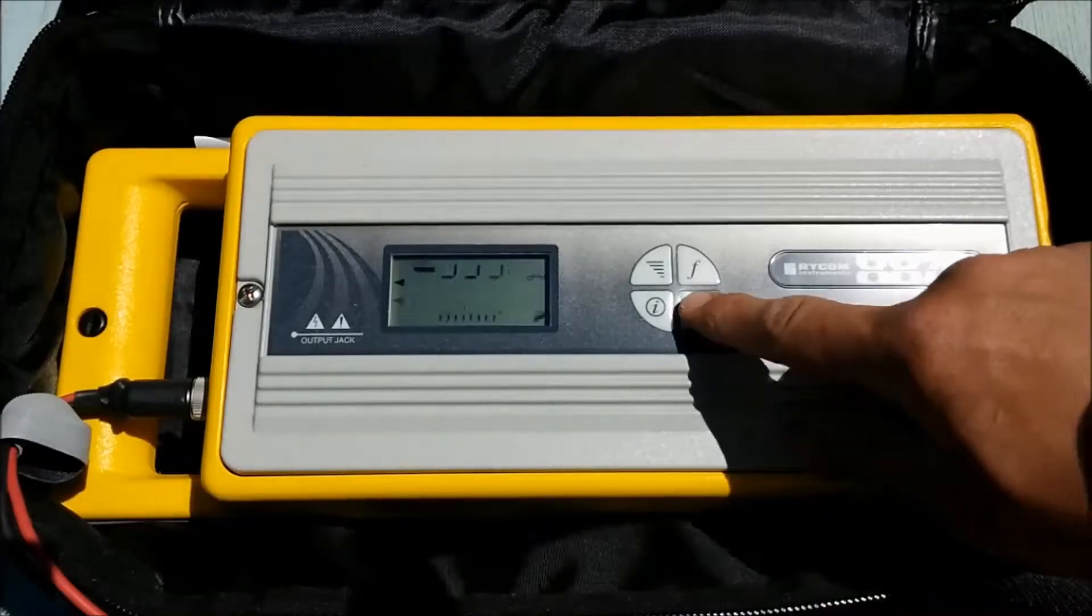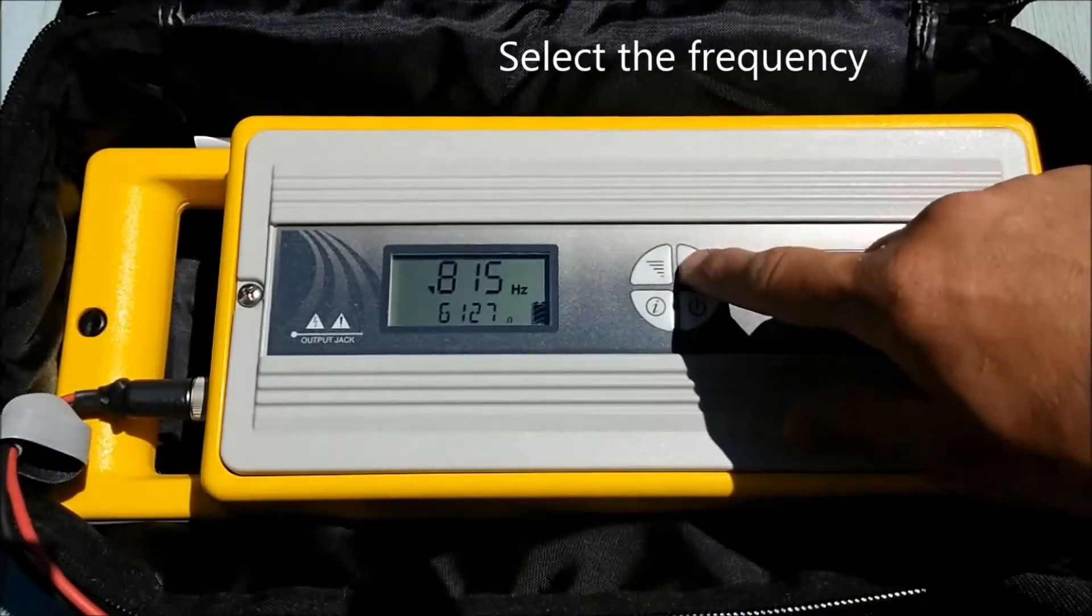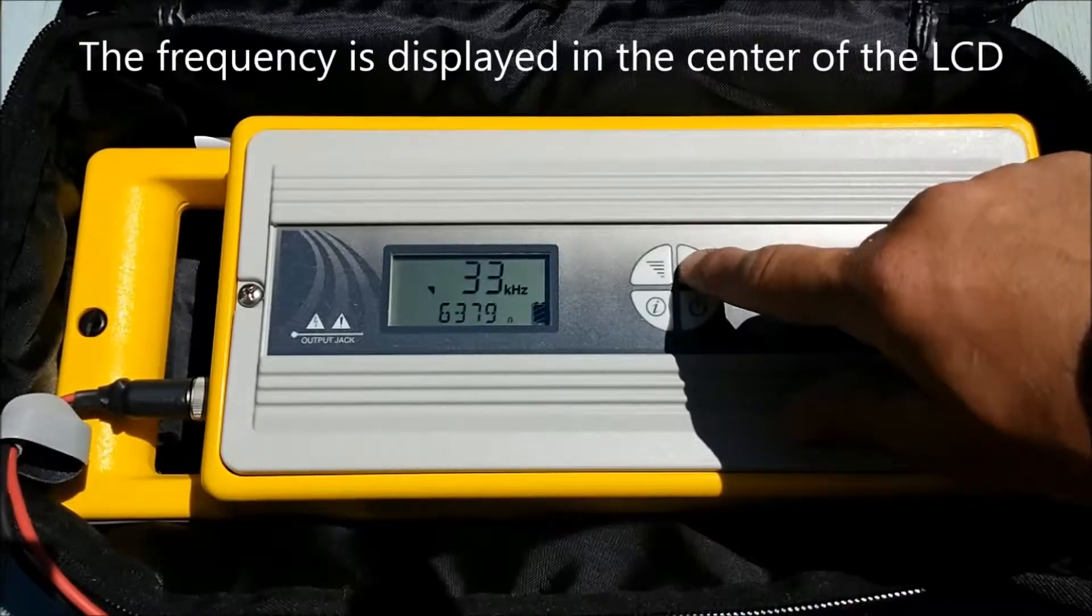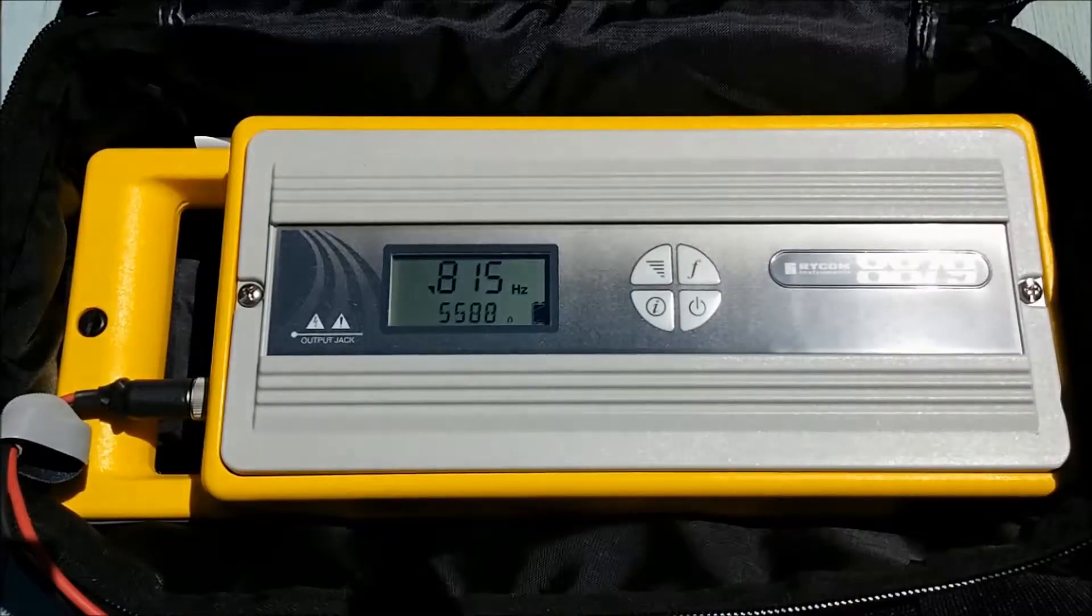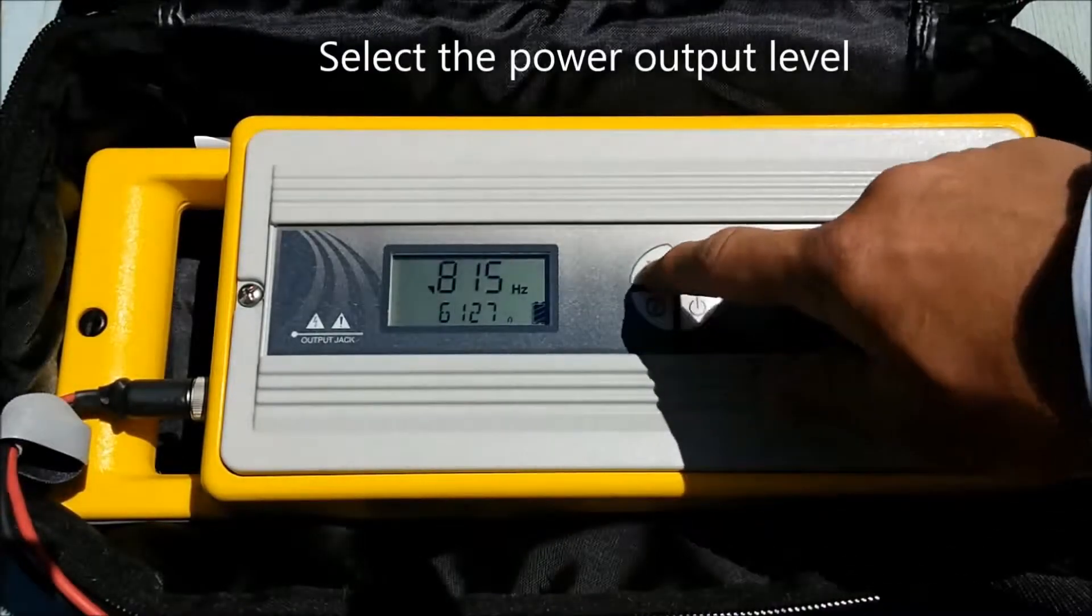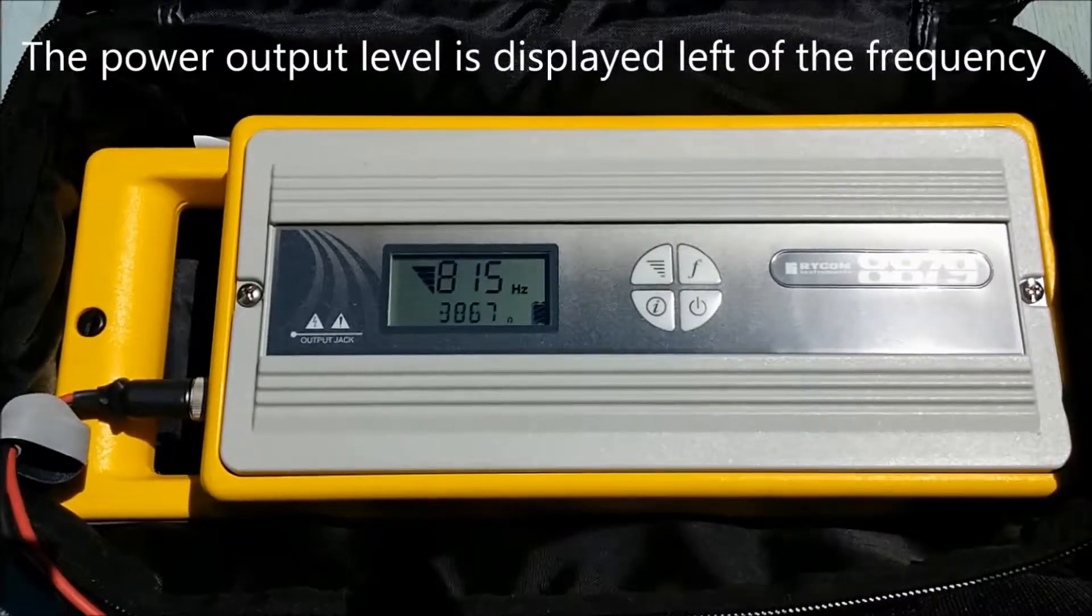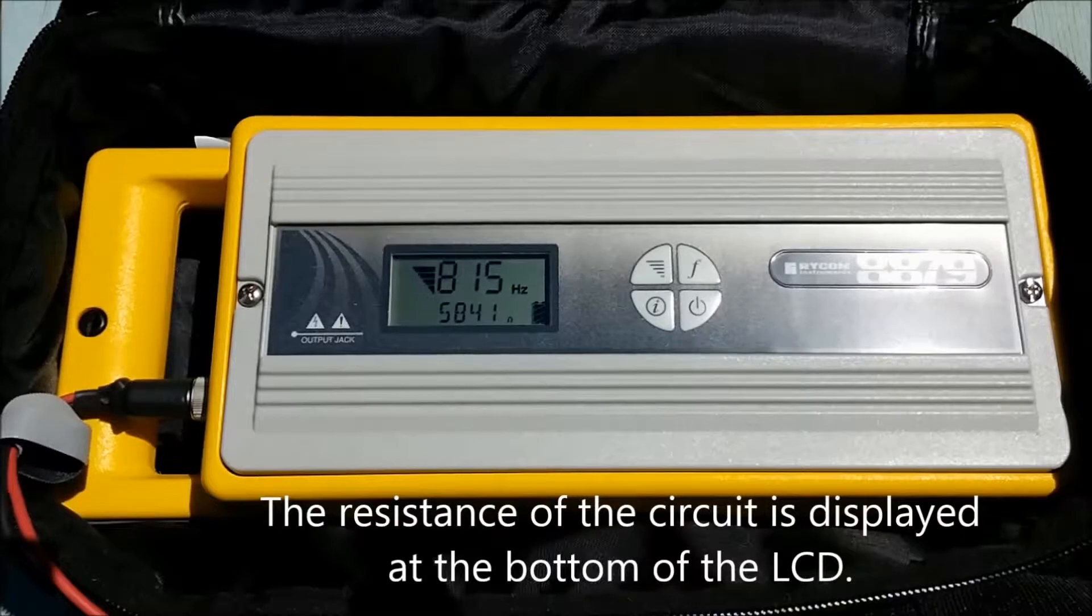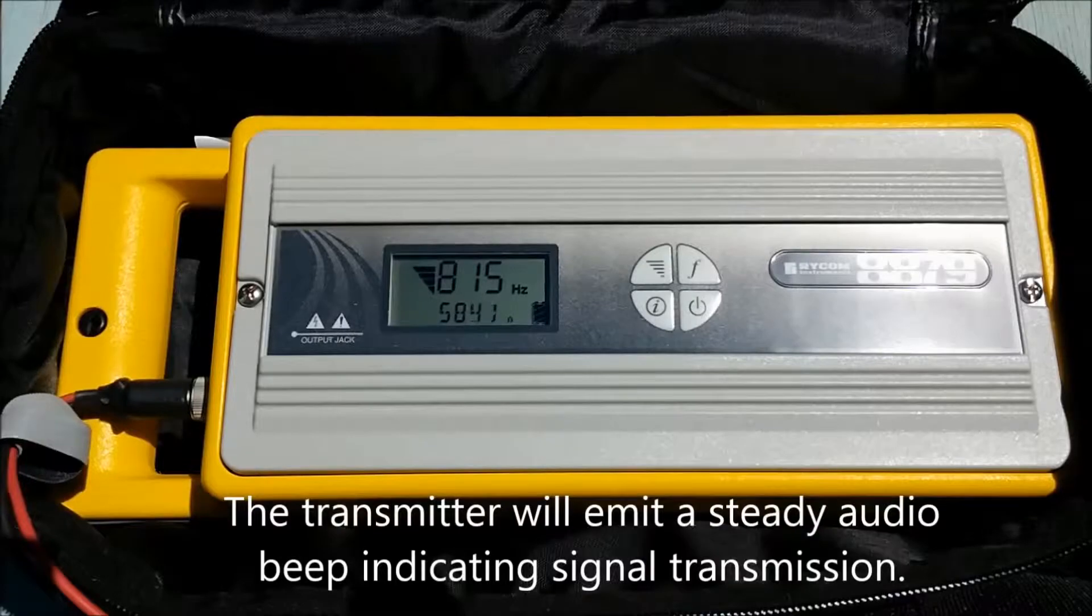Once the signal application method has been applied, turn the transmitter on. Using the frequency button, select the desired locate frequency. The frequency is displayed in the center of the LCD. Once the desired frequency has been chosen, select the power output level. The power output level is displayed left of the frequency. The resistance of the circuit is displayed at the bottom of the LCD. The transmitter will emit a steady beep indicating signal transmission.